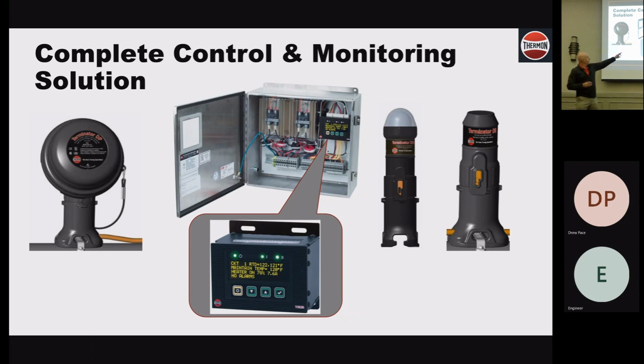So that's that. Lights. If you're not going to get a control system, at least get a light. They go on the end of the cable. They're good for tubing bundles. They're good for analyzer lines. They're good for any other heat trace line that's in your plant. It'll tell you that there's voltage at the end of the run. It's a feel good, right? It doesn't mean the cable is working. It doesn't mean your amp draw is appropriate. It doesn't mean any of that, but it's better than nothing.